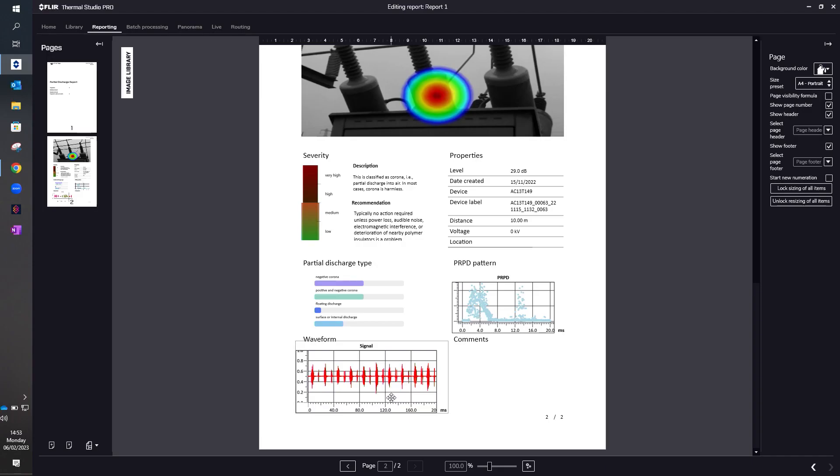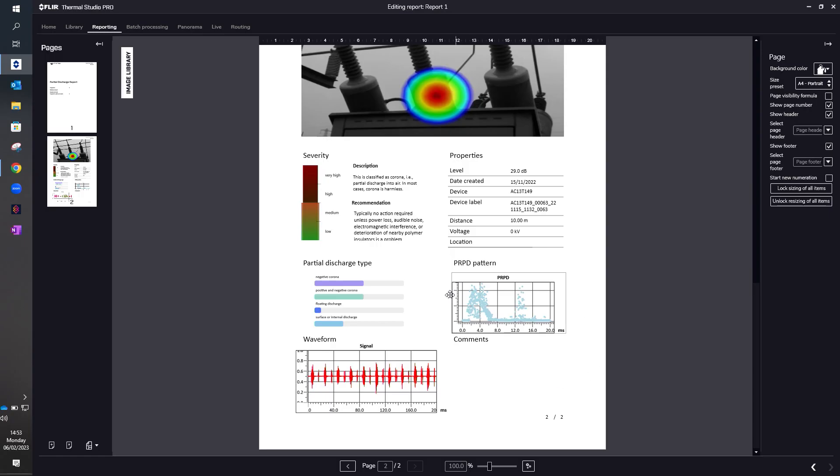We then move down to the waveform, which again is included in the report if you wish, and then we have a section on PRPD patterns, which is shown on the screen of the camera also. So as the partial discharge changes from one to another, the profile which is shown on the camera and shown in this section here will show a different profile.